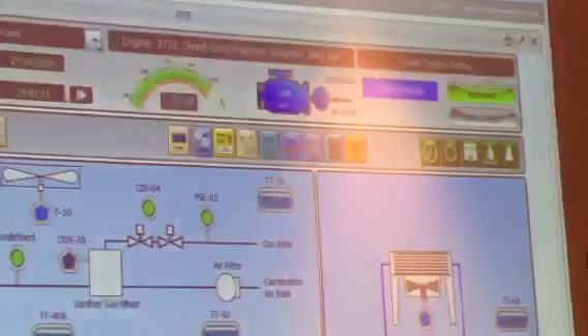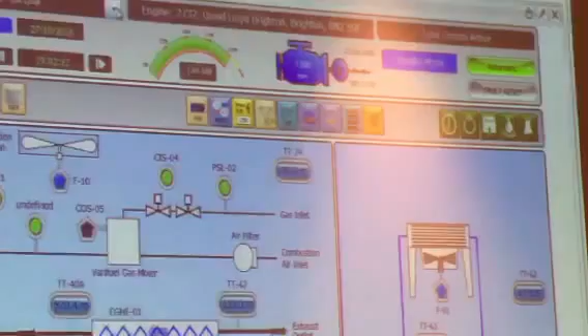We identify the machine by unit number and location up here, and it tells us that load control is active. The machine is generating in parallel mode and we're in automatic. If there was a fault, this would change the status, and the fault reset would allow us to remotely restart the unit and put it back on load.